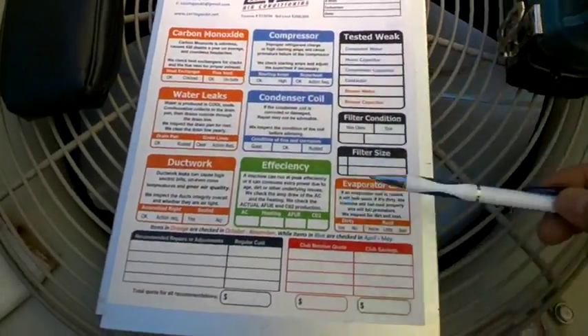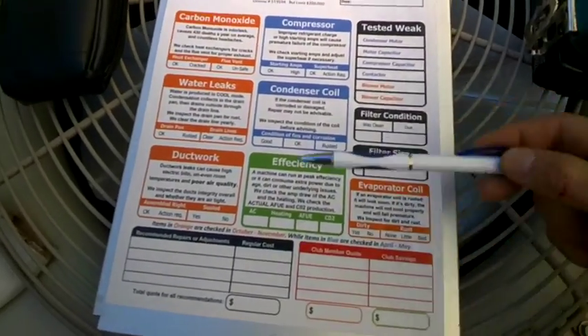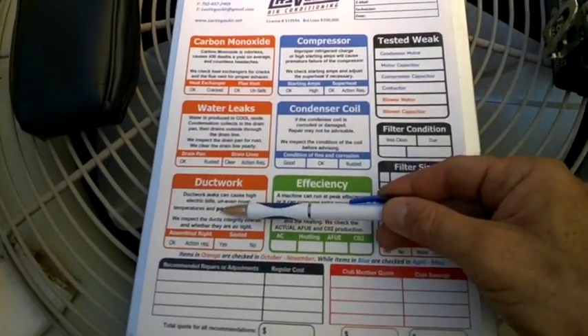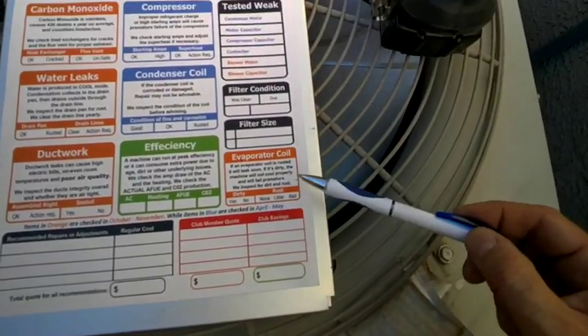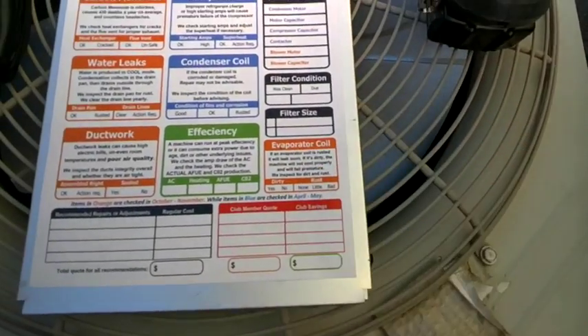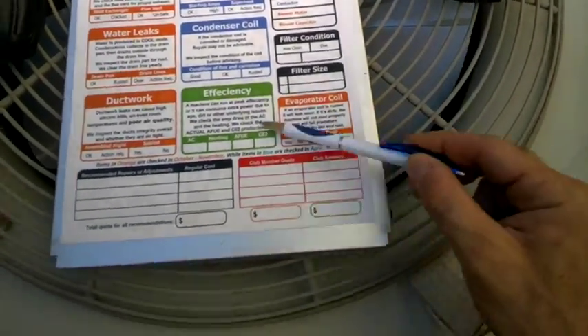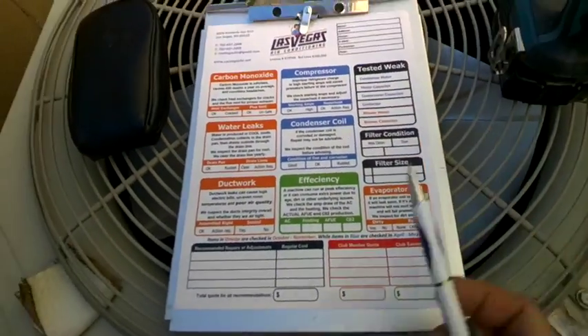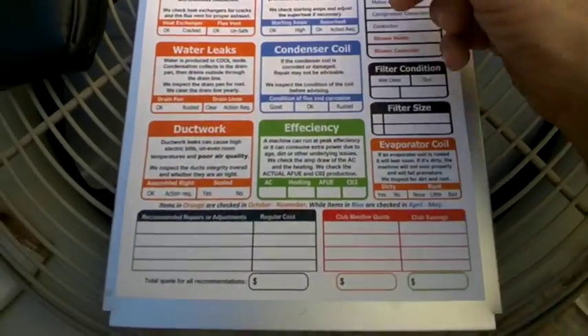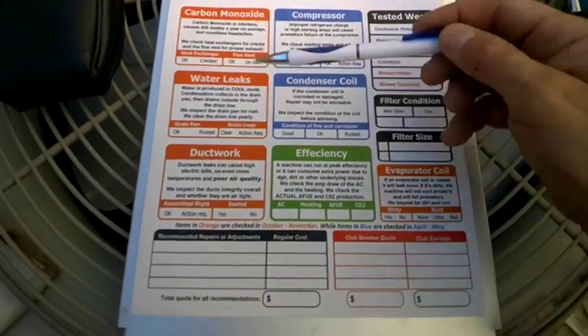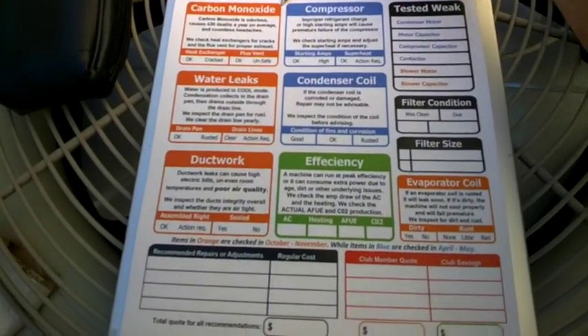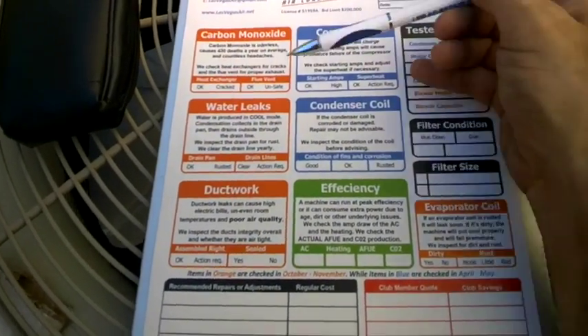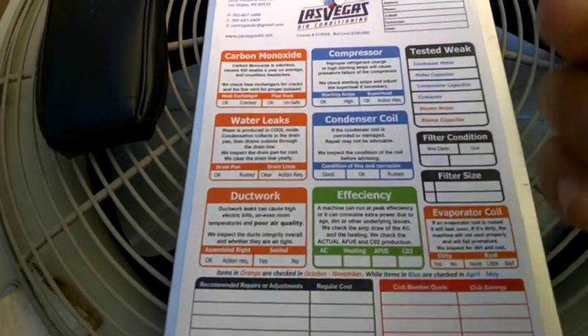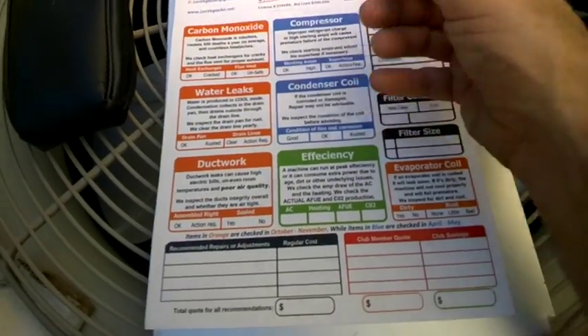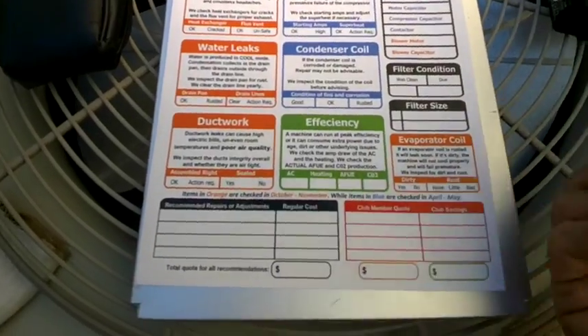Therefore, if we're in a maintenance contract or agreement with somebody, we come twice a year, inside, outside. Then we check these things all year round, and efficiency year round. The way it would work is it kind of draws the technician to the right points. So in the winter, he addresses carbon monoxide. He would check the heat exchanger or the flue exhaust and make sure it was all venting out properly.